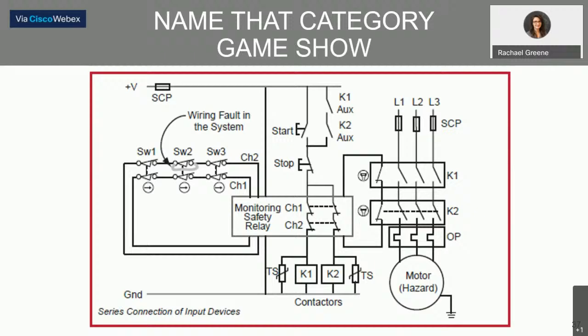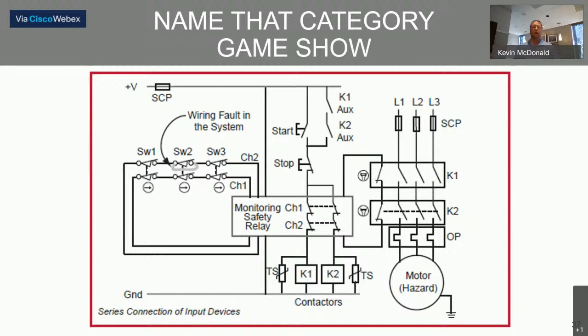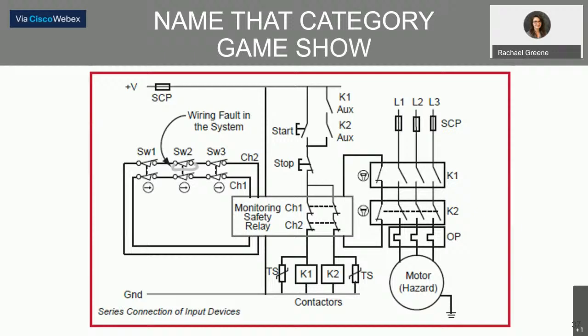Jeremy asks: how do categories relate to PL and SIL? They're part of it — the safety circuits are designed the same way when defining your performance level. There is a general corollary: Category 4 corresponds roughly to PL e, and Category 3 to PL d, but it's not always the case. There are scenarios where Category 3 with very high diagnostic coverage can still achieve PL e. But the general rule is: Category 4 is PL e.